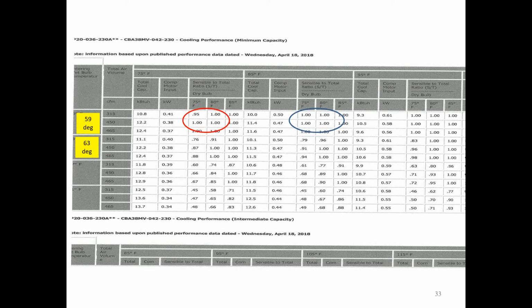Okay, as we get warmer outside, it still continues to be 100%. It gets worse actually. So what I want you to understand is if this unit is running at low capacity at 87, 88, 89 degrees outside because you oversized it, we're doing very little to minimal humidity removal. And that demand in the home continues to rise. And that's really what we're telling a customer. We're trying to make them more comfortable with this machine, and it can actually make it worse.